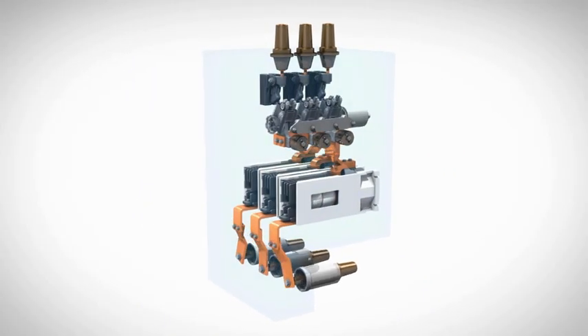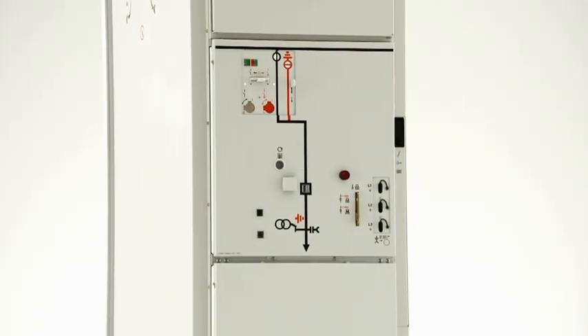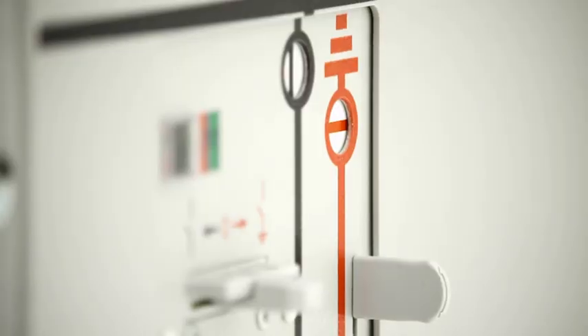Here the choose and execute principle ensures faultless operating sequences. Choose and execute means that the three position disconnector can generally be operated only when the circuit breaker is in the open position.